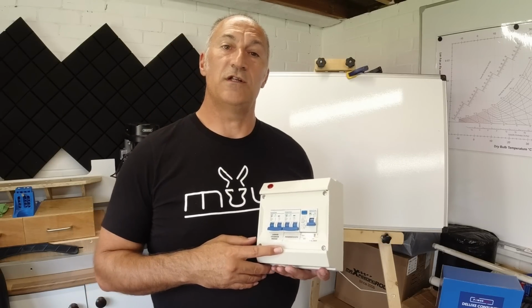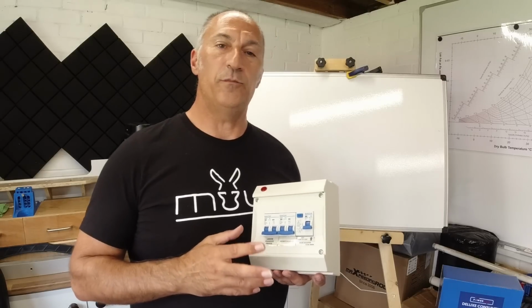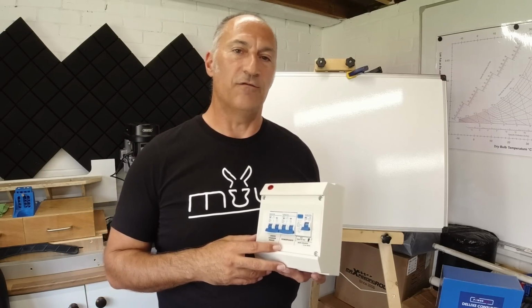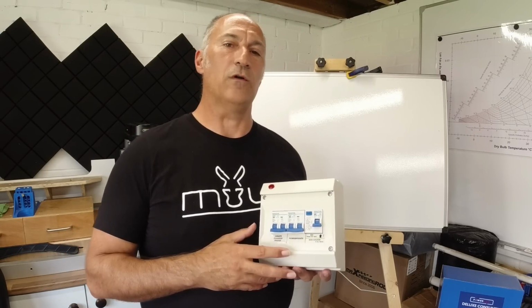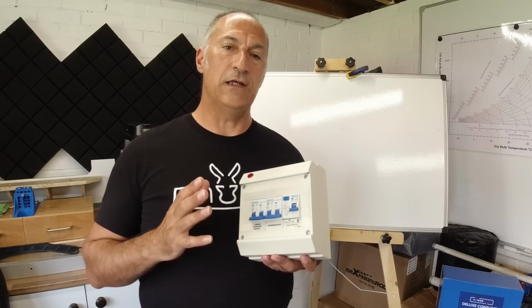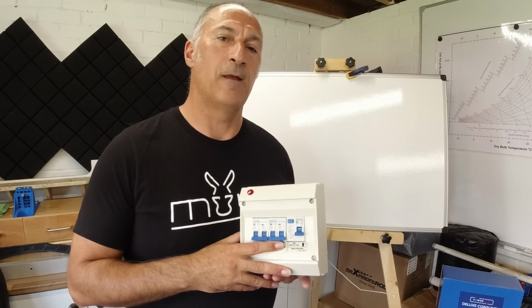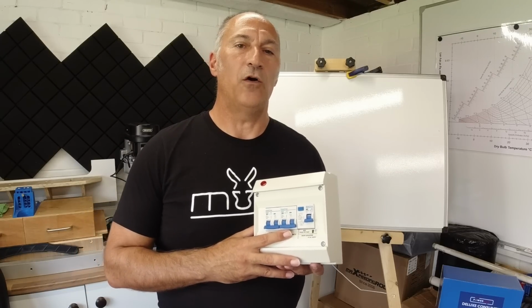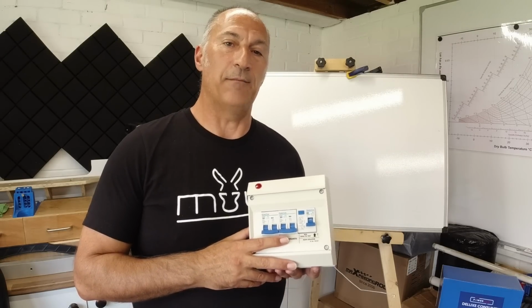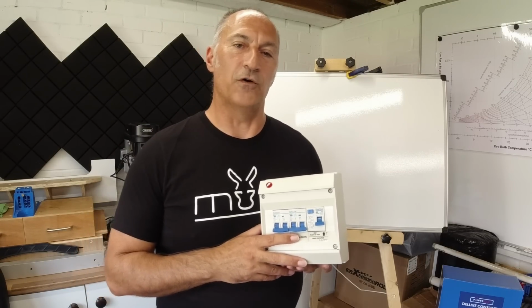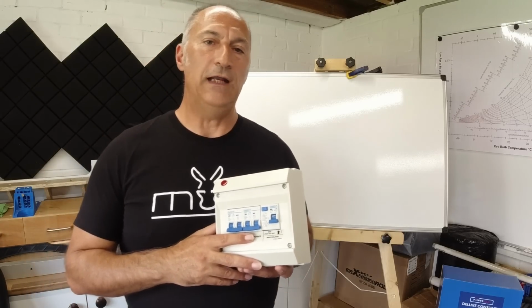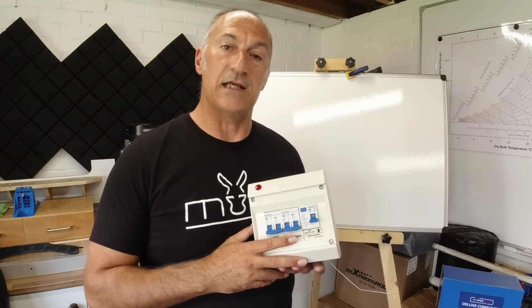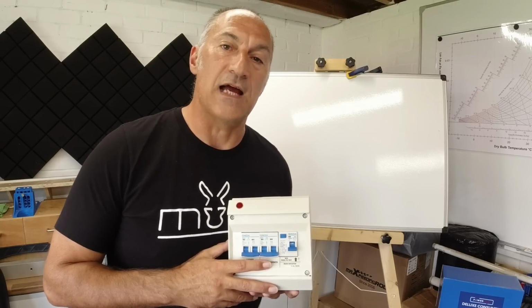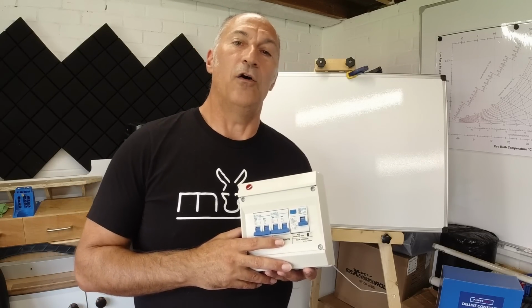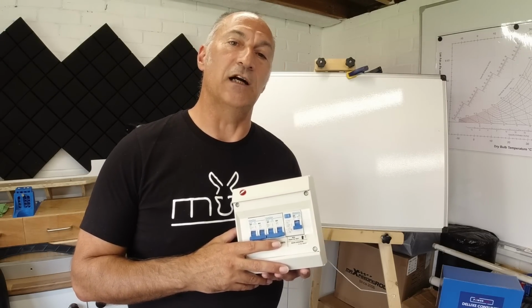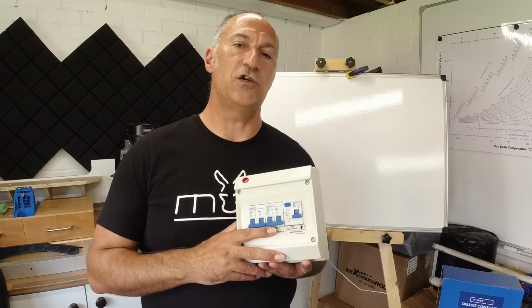And finally, I just want to touch on the fact that there could be, in your installation in your van, a situation, depending on what type of equipment that you've got, where you would need more than one consumer unit. For instance, you're definitely going to need one on the incoming hookup supply coming into your van. So we've just gone through that, that's a definite. But then if you've got an inverter which takes the 12 volt DC from your leisure batteries and converts that to 230 volt mains, on the discharge side of that inverter, you could possibly need another consumer unit.